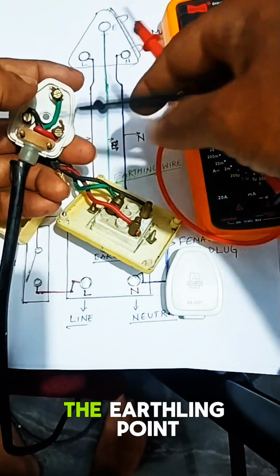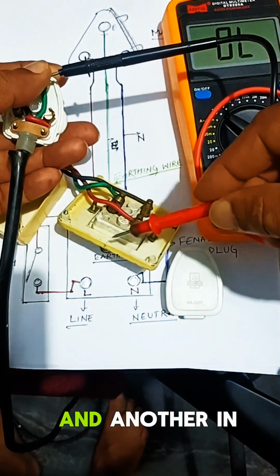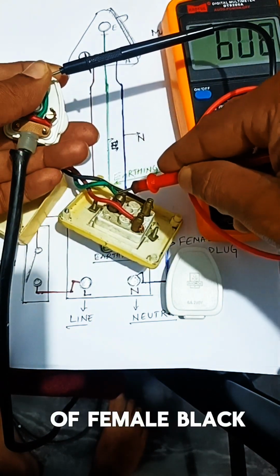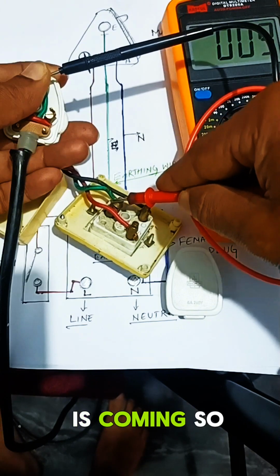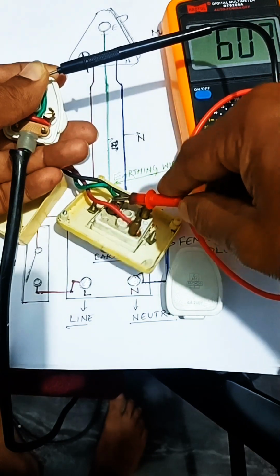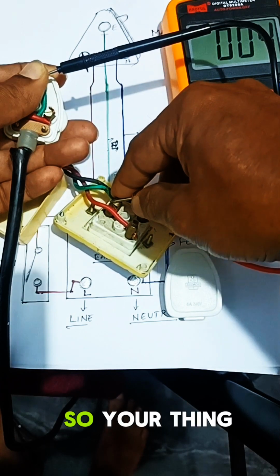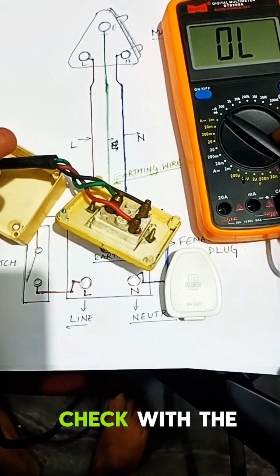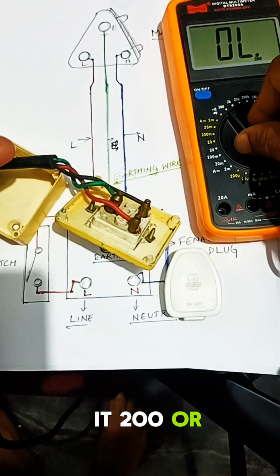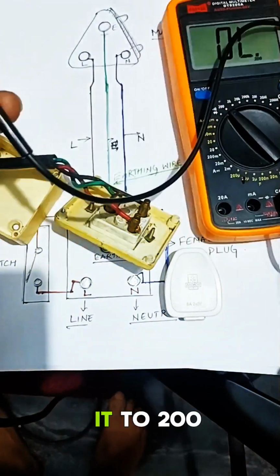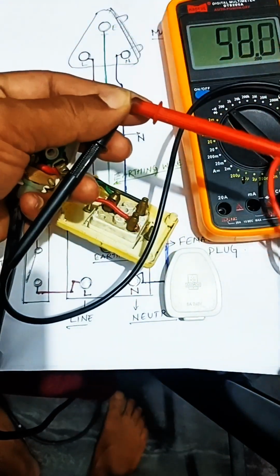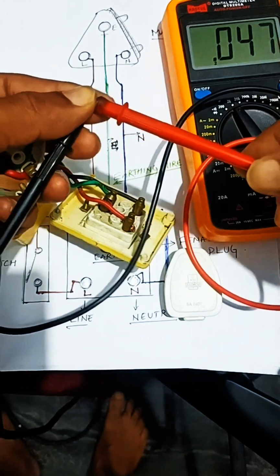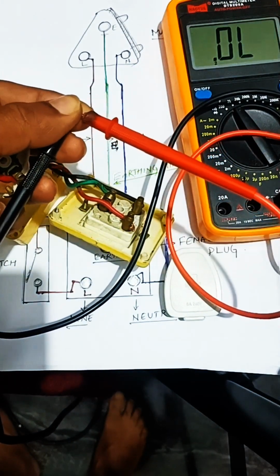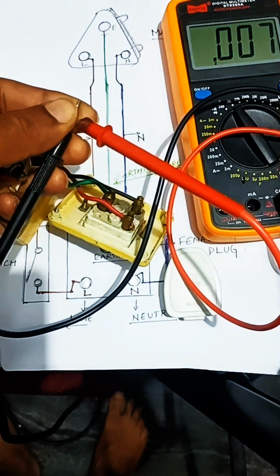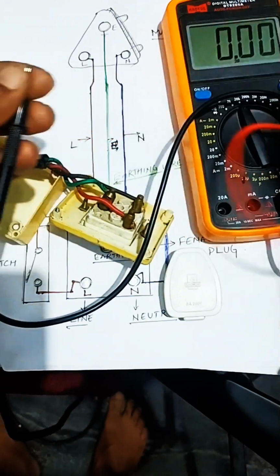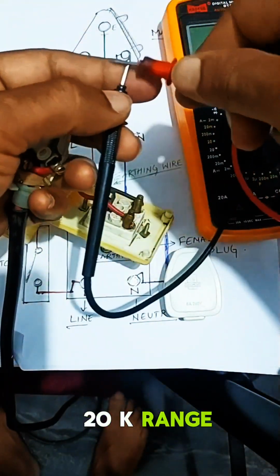Now you have to check the earthing point. Keep one probe on the earthing connection and another on the earthing point of the female plug. Here the beep is coming, so your earthing point is good. Next you can check with the resistance mode also. You can keep it in the 200 or 2k range and check whether continuity is there. I have kept it to 200 ohm range and check here. I'll keep it to 2k. Or 20k. So I have kept it to 20k range.